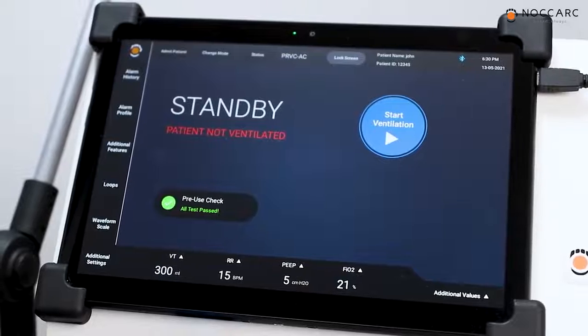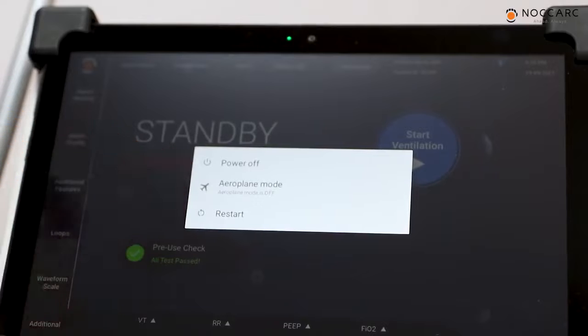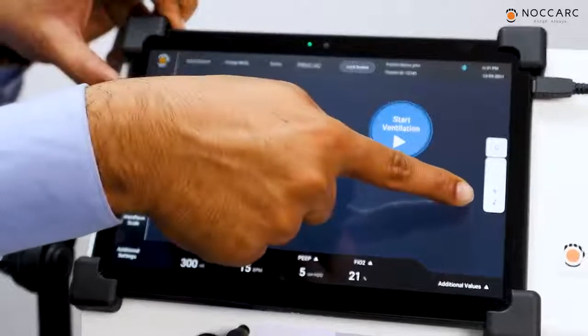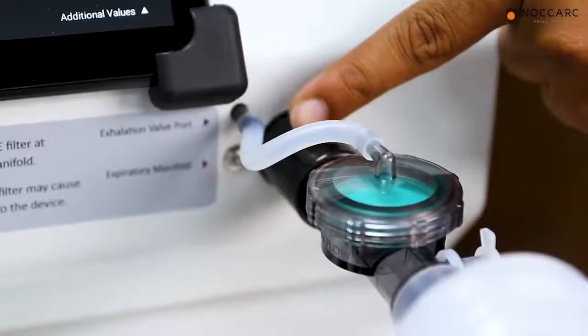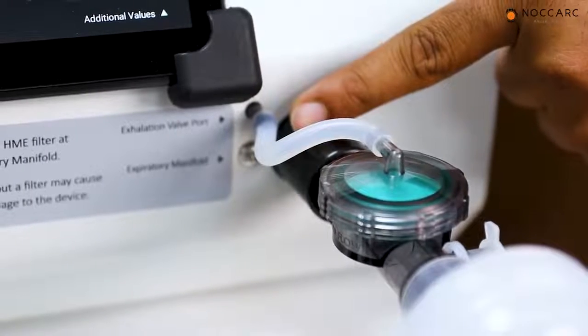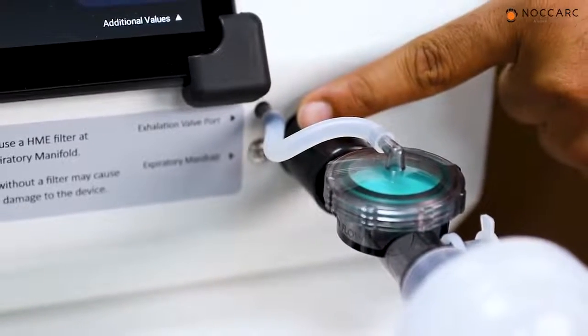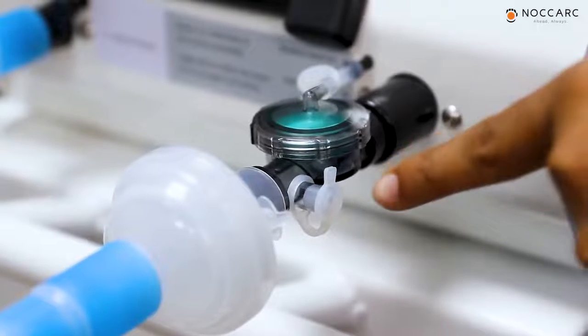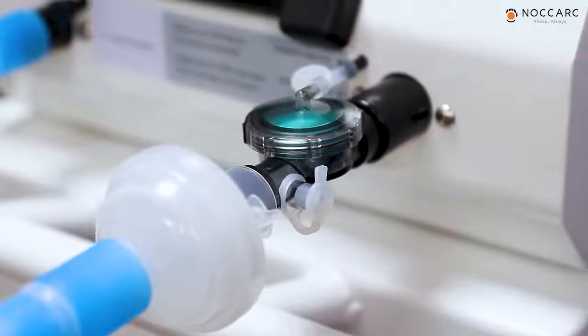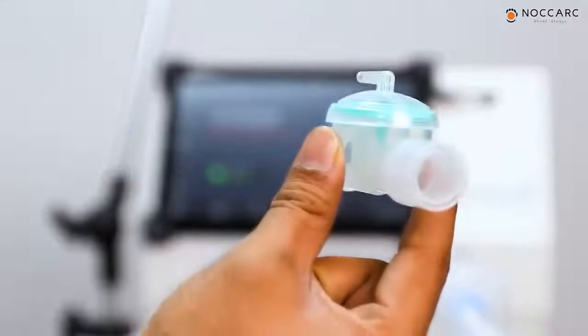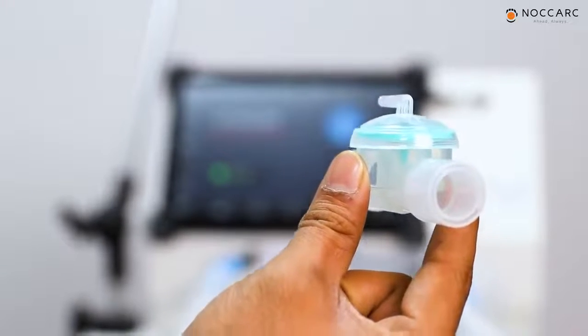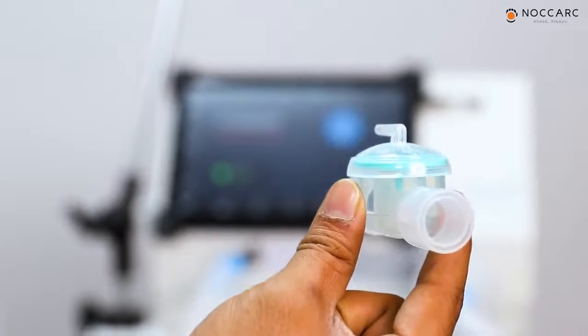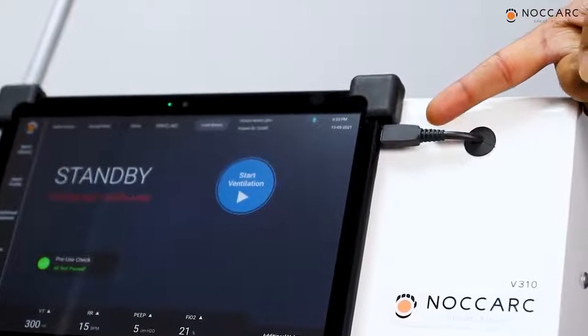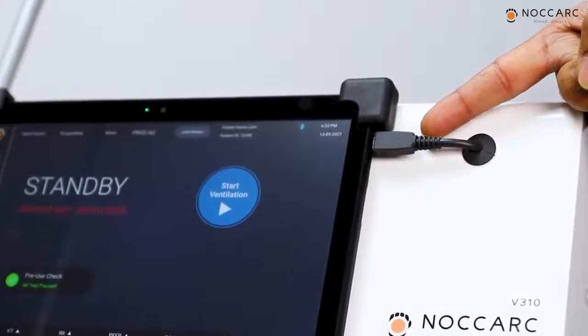Now we are going to see don'ts for Noccarc V310. Never turn on aeroplane mode. Never mute the alarms. Never remove the silicone tube connected between active exhalation valve and the exhalation valve port. Never remove the knob cover provided on active exhalation valve and HME filter. Never use disposable active exhalation valve on multiple patients. Never remove the D-type charging cable connected with UI screen.